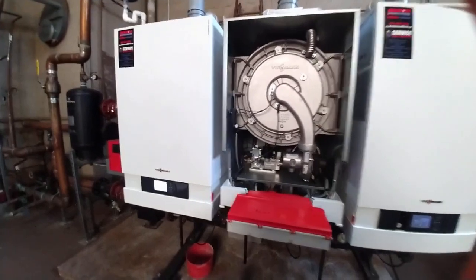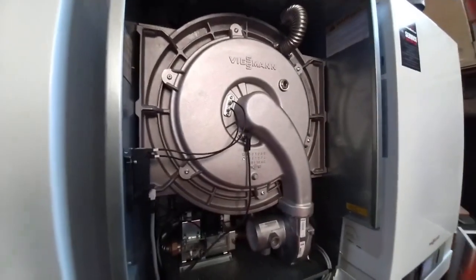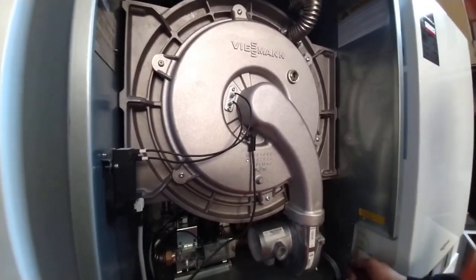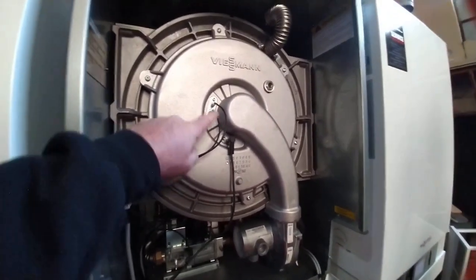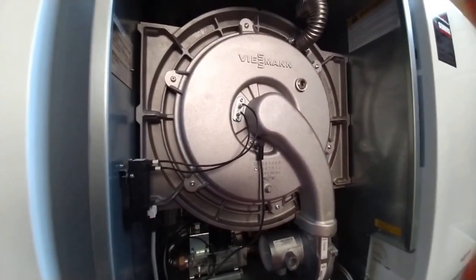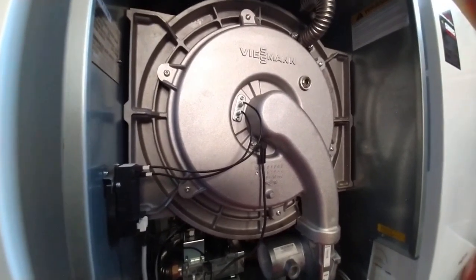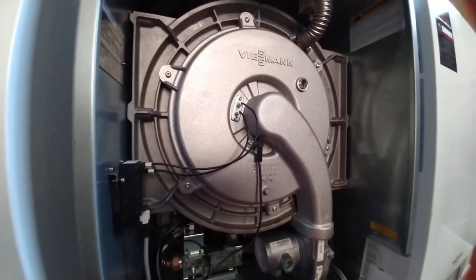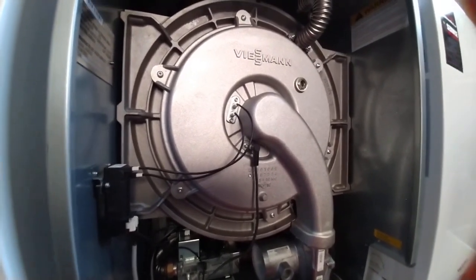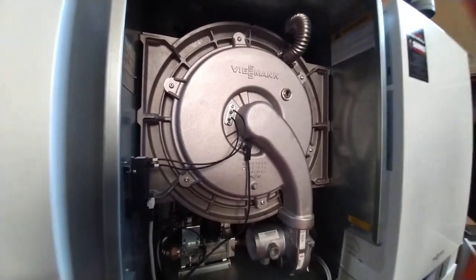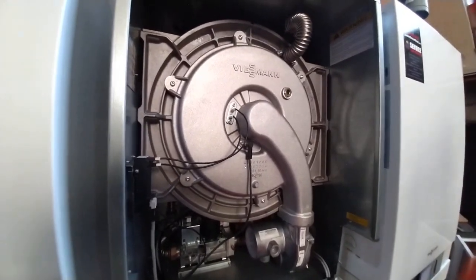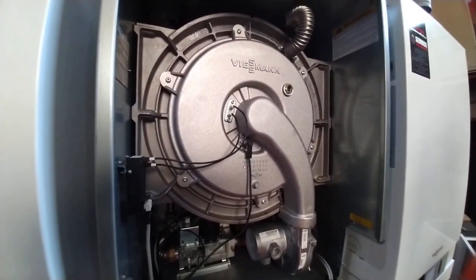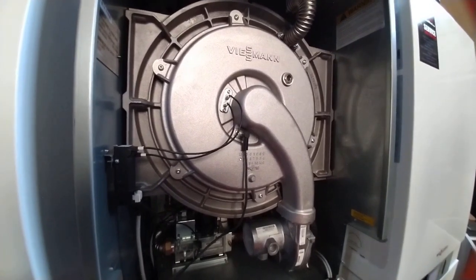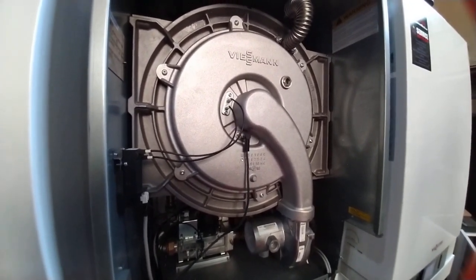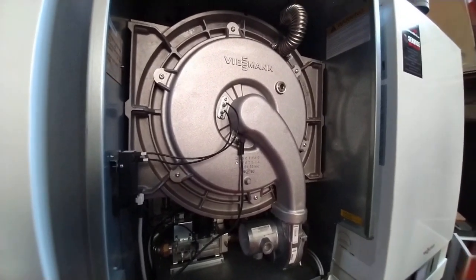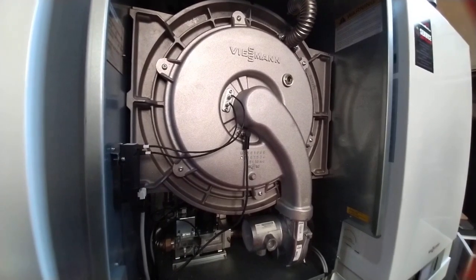Another extremely important item to check on an annual basis is the heat exchanger itself and what it looks like inside. We can check the igniters and flame rods by pulling them out without pulling the whole cover off of the heat exchanger, but we want to examine the heat exchanger and the burner, look at the condition of those, and properly clean them to make sure that this boiler stays in good condition. A high efficiency boiler neglected for as little as 5 or 6 years, you can literally compromise the whole life of the boiler and need to replace it. This should last a good 25 or 30 year lifetime if we do the proper maintenance. So we're going to disassemble this, take a look at it, do the proper cleaning, and see what condition it's in.